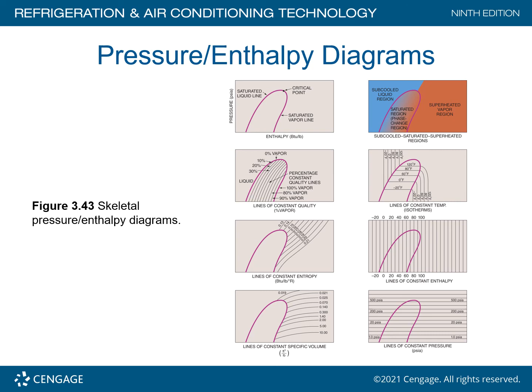So we can take this and plot, and see what the refrigeration air conditioning system is doing by utilizing these charts, measuring the temperatures and recording the pressures. I can't stress enough, you must have accurate instruments in order for this to happen. If you do not have accurate instruments, you are going to get bad readings. You're not going to be able to plot a system.